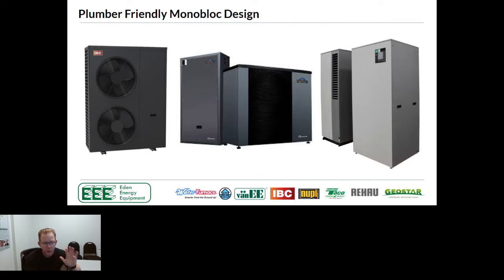What IBC is doing a little bit differently is they have an outdoor unit, and they have some really, really cool control logic that they're going to be launching later in the year that they don't actually need an indoor unit. So they're doing it very, very creatively. And at a future webinar, we'll talk more about controls on heat pumps. The one in the middle is the Enertech. And the idea of the Enertech unit, and actually the System M on the right-hand side of the slide, is these units have indoor and outdoor units. So the concept of this would be is if you've never done a hydronic heat pump before, you may want to consider doing a packaged unit with an indoor and an outdoor.